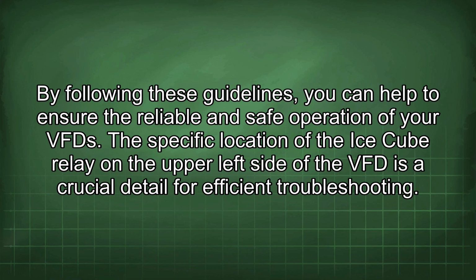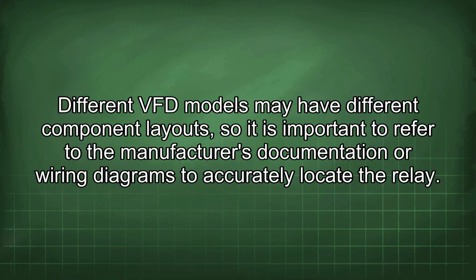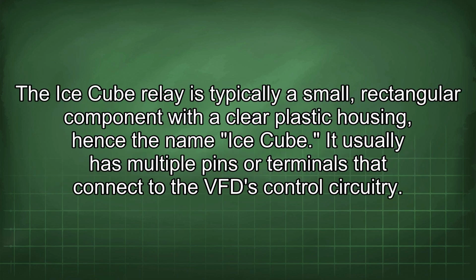The specific location of the ice cube relay on the upper left side of the VFD is a crucial detail for efficient troubleshooting. Different VFD models may have different component layouts, so it is important to refer to the manufacturer's documentation or wiring diagrams to accurately locate the relay. The ice cube relay is typically a small, rectangular component with a clear plastic housing, hence the name ice cube. It usually has multiple pins or terminals that connect to the VFD control circuitry.